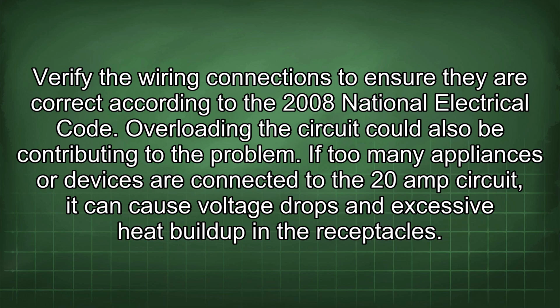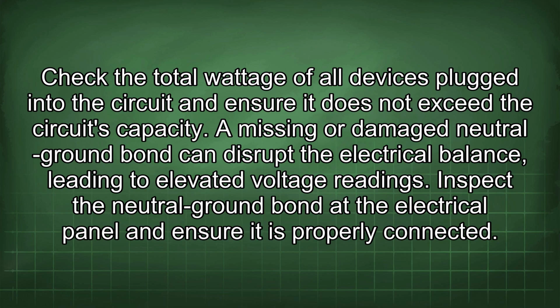Overloading the circuit could also be contributing to the problem. If too many appliances or devices are connected to the 20 amp circuit, it can cause voltage drops and excessive heat build-up in the receptacles. Check the total wattage of all devices plugged into the circuit and ensure it does not exceed the circuit's capacity.